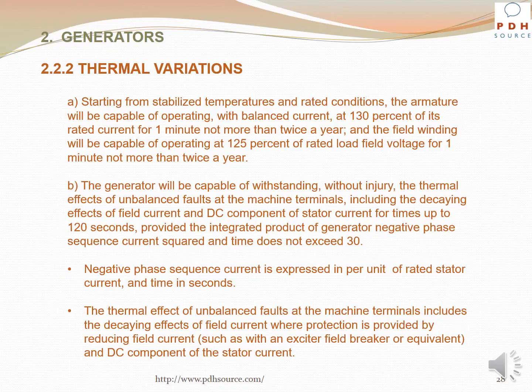With regard to thermal variations, starting from stabilized temperatures and rated conditions, the armature will be capable of operating with balanced current at 130% of its rated current for 1 minute, not more than twice a year, and the field winding will be capable of operating at 125% of rated load field voltage for 1 minute, not more than twice a year.